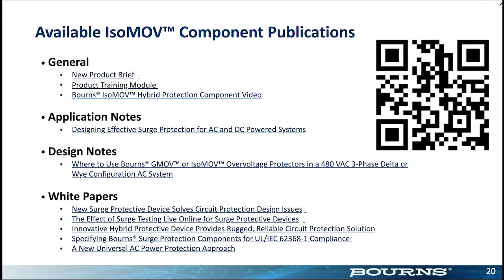The question we have here is, can you lower the clamping voltage by putting multiple IsoMOVs in parallel? Yes, you can, but a rule of thumb that I use is that you don't really double when you put two in parallel. For example, if you take a 3KA and a 3KA and put them in parallel, typically you would say they should handle 6KA. But because they are not matching, even with the MOV, unless you match it really well, you still have one that will clamp before the other. So to be on the safe side, we always say the first one will probably take 60% of the surge, and the remaining 40% will be on the second unit. So if you put them in parallel, yes, you can increase the surge rating, but keep in mind that it's not really double.